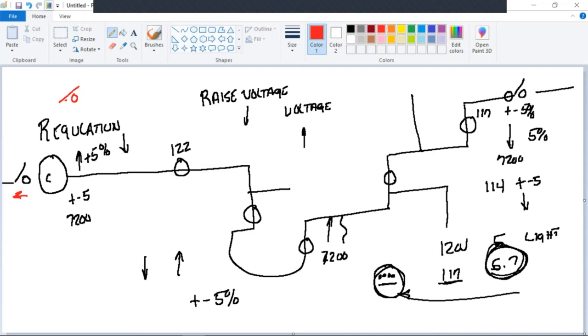Now, say I did need to do that maintenance, and I'm just going to do it here as an O. So I unbolted it from the regulator. I've got an open point on this side. In order for me to now regulate the circuit, and this is the one that I put here earlier, I've got to use the other substation that I tied to over here. Otherwise, this open point would leave, that's going to take switching to take out an entire circuit.